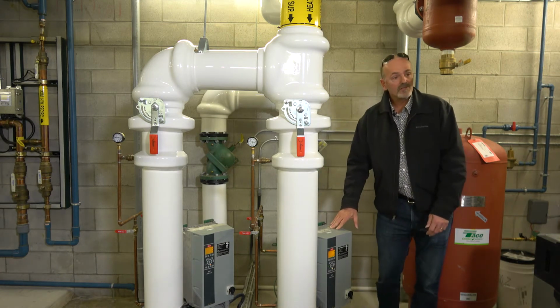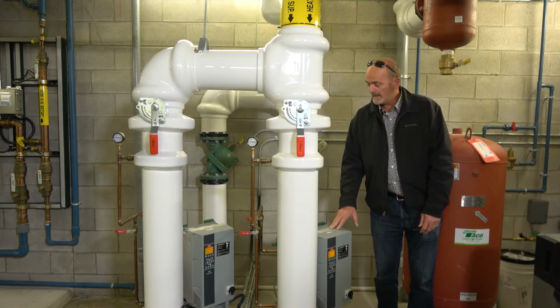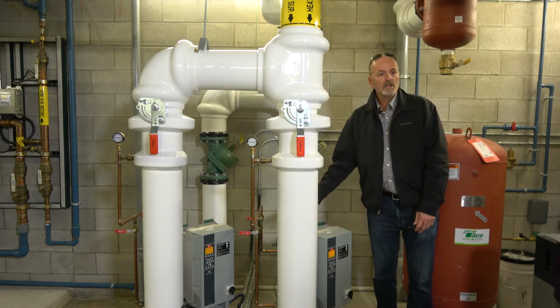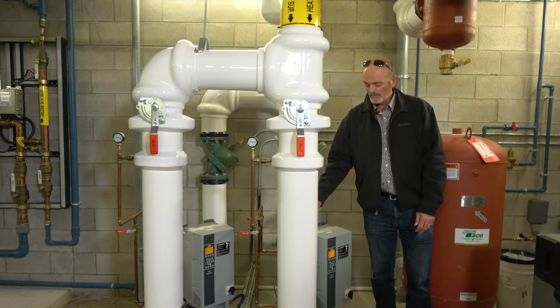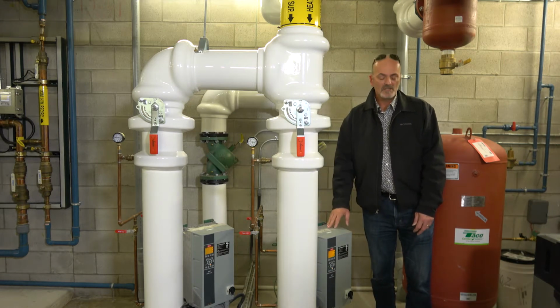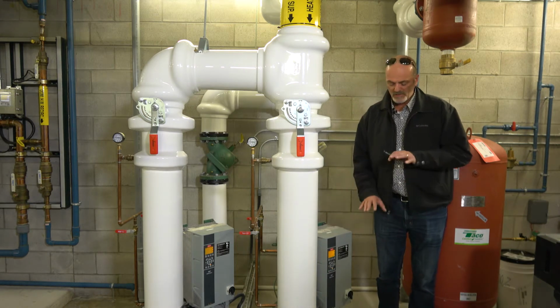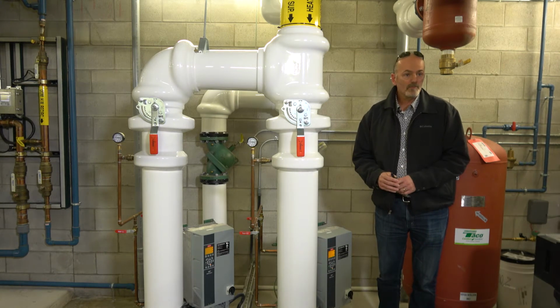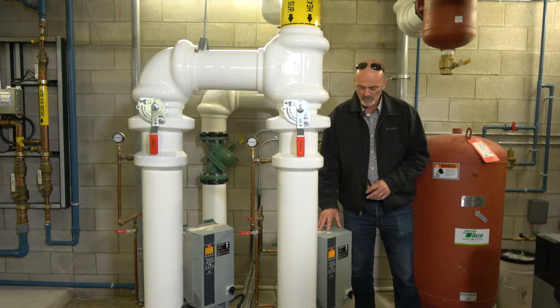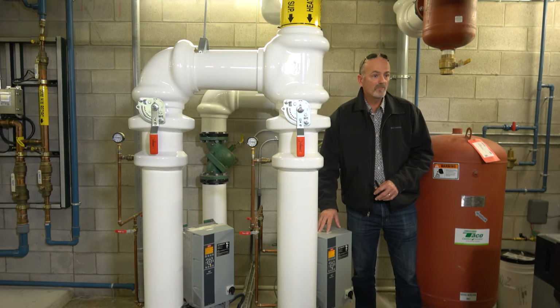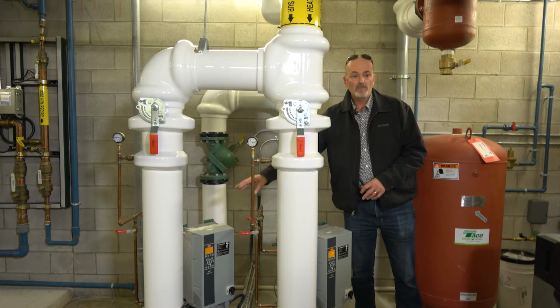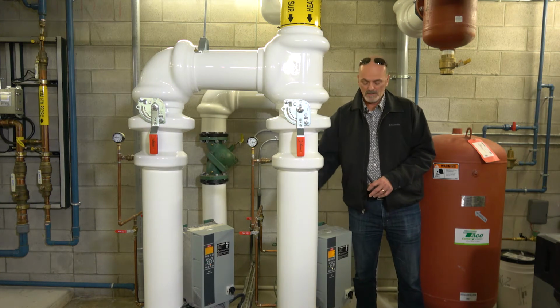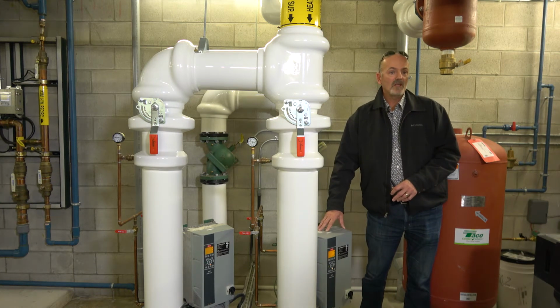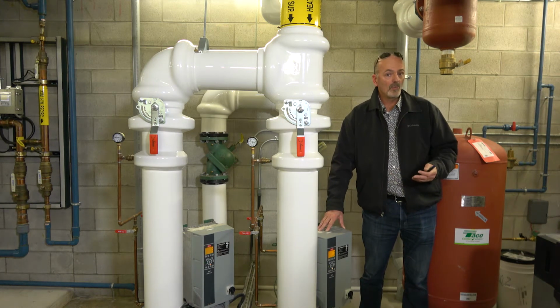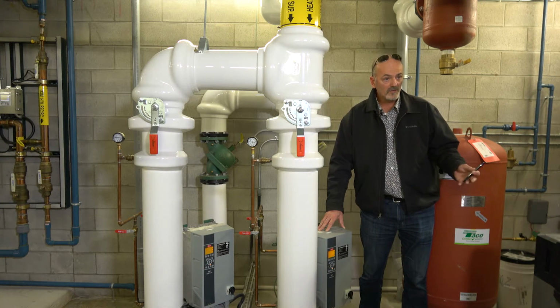These drives on each of the pumps, they basically are reading and reacting to system pressure based on motor amp, as I explained earlier, and they're speeding up and slowing down. The way it's set up to work is that there's one pump that runs, and that's your duty pump. The other pump is meant to be a standby. This runs, maintains, and it's designed to maintain the flow required in all conditions for the heating system.